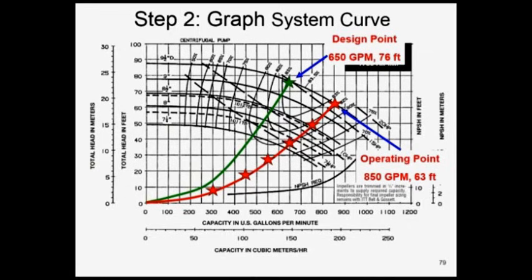So the red line with the red stars is the real system curve, the one that's really happening and giving you 850 at 63. The green line was what you thought was the theoretical system curve. It was going to give you 650 at 76. But the bottom line is we don't need 76 feet of head, do we? What's the goal here? Don't forget your goal. Your goal is to balance. Your goal is to get you to 650 GPM. That is your goal.